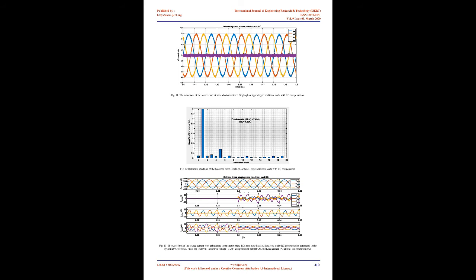Fig 9 demonstrates the system current harmonics for single-phase type 1 before the proposed control has been connected to the system. Fig 9, waveform of the source phase and neutral current with balanced three single-phase type 1 loads. The neutral and phase currents have the same magnitude of 7.52 A. However, the phase lines are distorted with odd harmonics, i.e. 3H equals 71.53%, 5H equals 33.63%, 7H equals 9.71%, and 9H equals 7.99%, and a total current harmonic distortion of 80.32% as shown in Fig 10. The neutral line is distorted only with the zero sequence current.